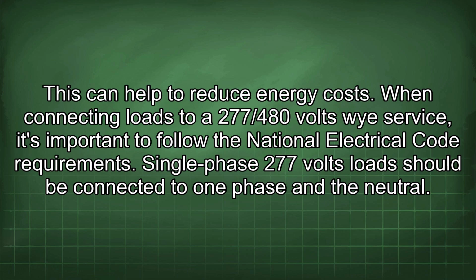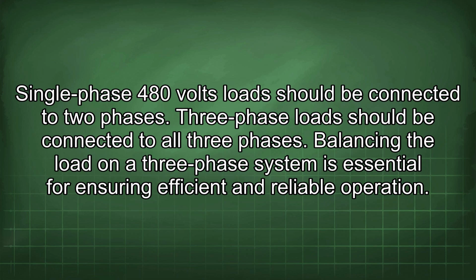When connecting loads to a 277/480 volts Y service, it's important to follow the National Electrical Code requirements. Single-phase 277 volts load should be connected to one phase and the neutral. Single-phase 480 volts load should be connected to two phases. Three-phase load should be connected to all three phases.